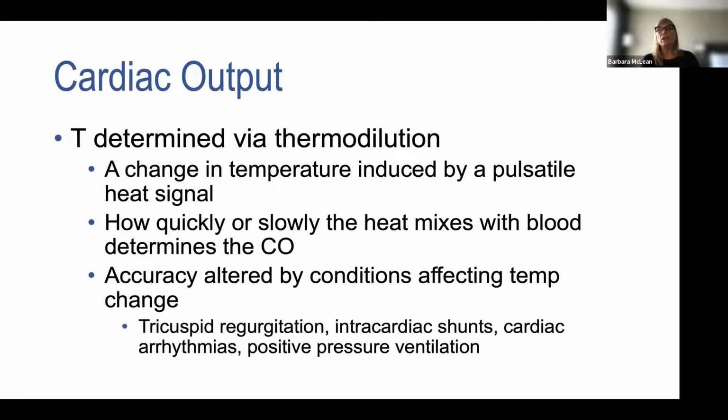And the same kind of things are affected here. The difference between continuous cardiac output monitoring and bolus thermal dilution is that it's heat and it's not user affected. Bolus cardiac output is using cool fluid, just room temperature fluid, which is also very affected by the user who's operating the methodology, how quickly they pushed it. Did they push it at the right time? Did they hold the barrel of the syringe in their hand and make the injectate warmer? So there's a lot of variables that affect bolus thermal dilution that are not nearly as important in continuous thermal dilution.